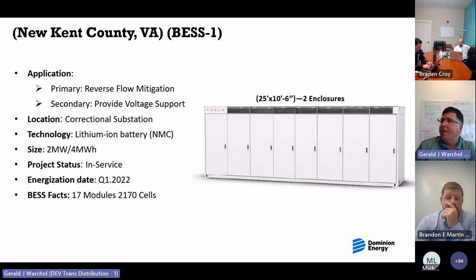Okay. So a little more on the specifics of the energy storage system at the correctional substation. You essentially have 2 Megapack containers sitting on a concrete pad. This was all built in-house by our substation department with a little bit of help from the vendor. Every energy storage system will have a bidirectional inverter associated with it, and that inverter takes DC power and inverts it to AC, or takes AC and rectifies it to DC for charging the batteries. The inverter systems for the Tesla Megapack are equipped inside the container. We leave the inverters with sets of 500 kcmil cable. We come to a metering cabinet, which is essentially a point where we tap off voltage and current signals for controlling the battery, telling the brains of the battery, the TSC, the Tesla site controller, where it's at and whether it's putting out the right set point.